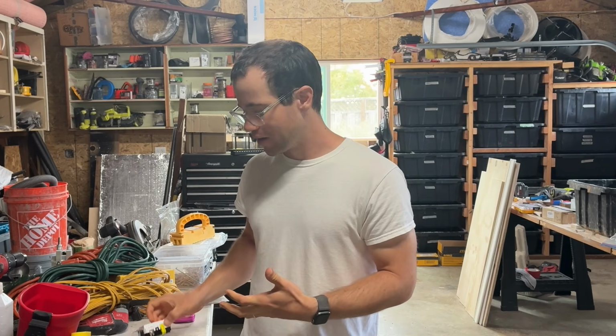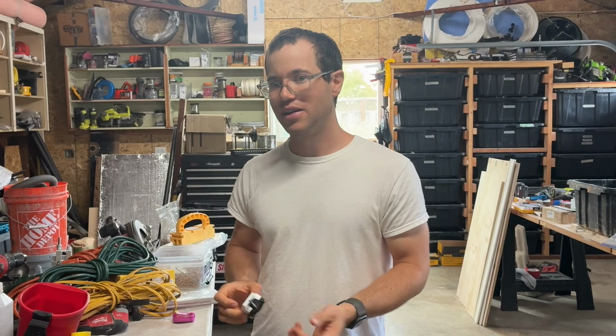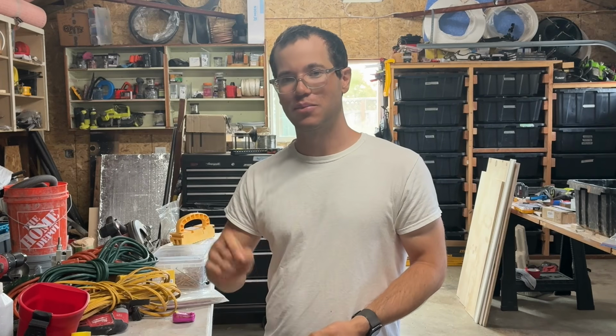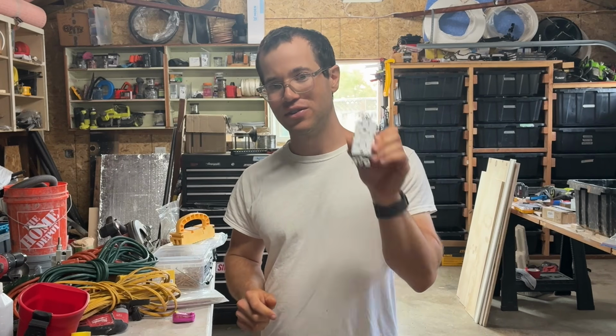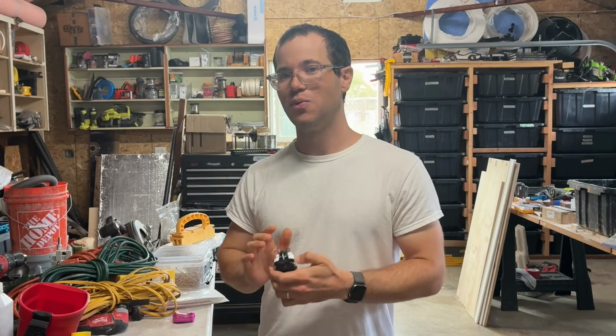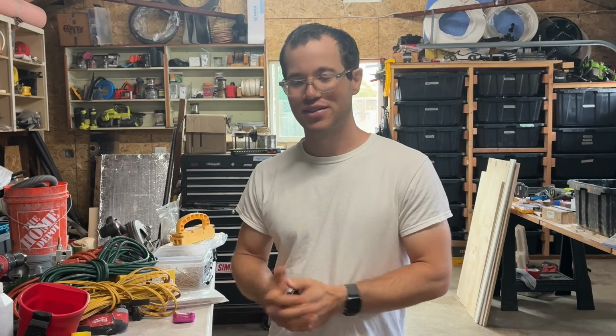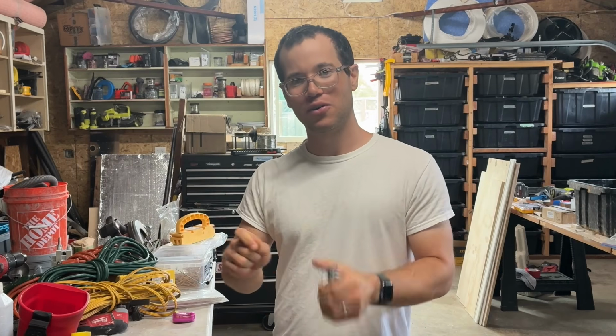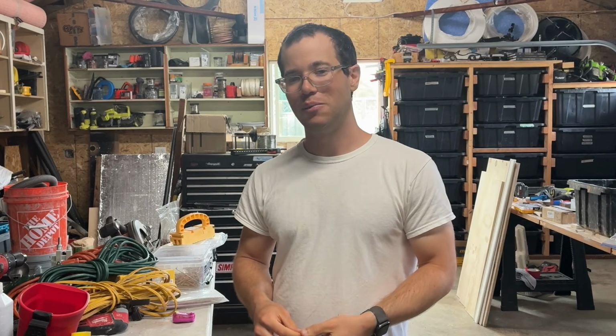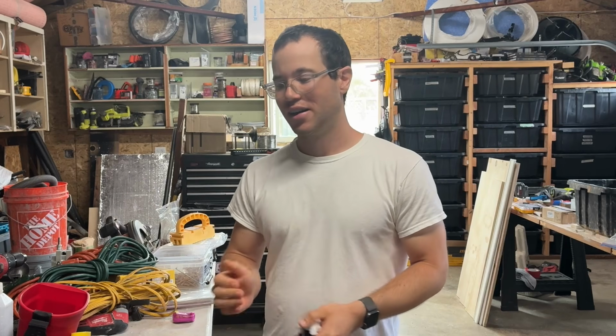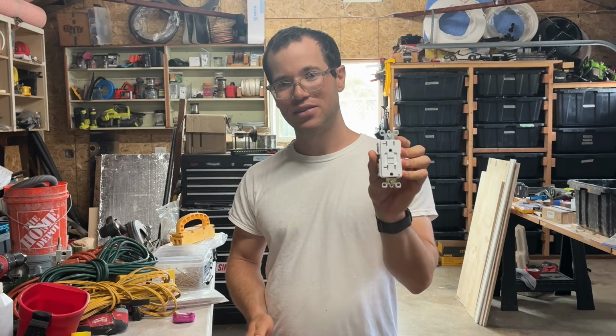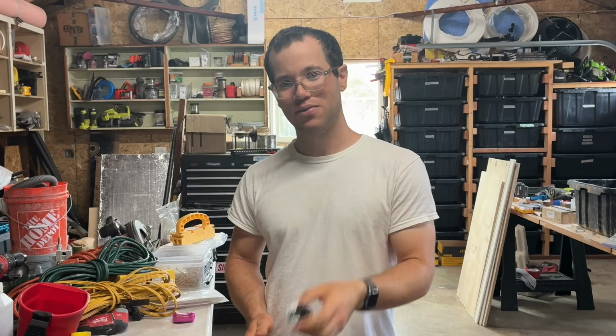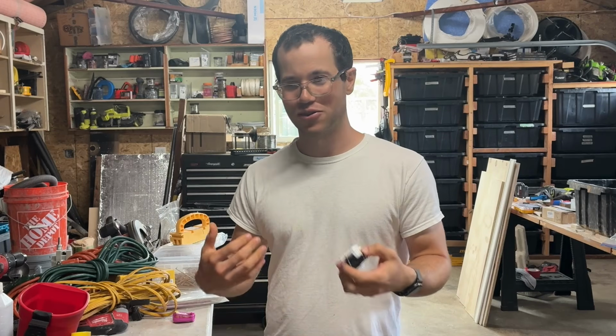Every time on older houses you replace something, if you don't see that bare copper ground wire, you need to install one of these, unless you want to rewire your entire house with modern Romex wiring that has a ground wire running all the way back to your sub and main panel and the ground rod. That's why these are the cheap alternative to rewiring a whole house, which can cost tens of thousands of dollars.